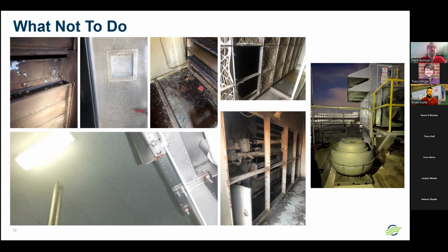It's just one more reason why we like to get on site after the install so that we can make sure the proper education and understanding is in place at the end user level, so that they're, number one, taking care of their unit as they should be, incorporating it into their preventative maintenance schedule, but also making sure the sequence of operations is running as it was originally designed. If we need to make design changes at that time, obviously that's a good time to do that. But we definitely don't want to see conditions like what are shown in these pictures. And then really from there, it's kind of a cascade effect. Sometimes we'll see missing filters. Air takes the path of least resistance, right? So the rest of these filters probably aren't doing a whole lot.